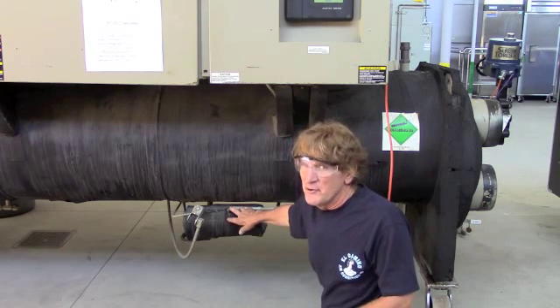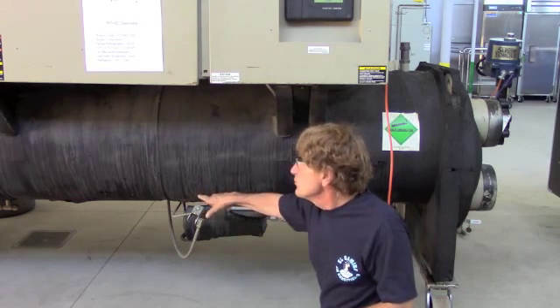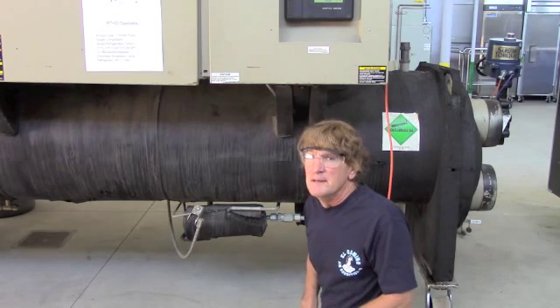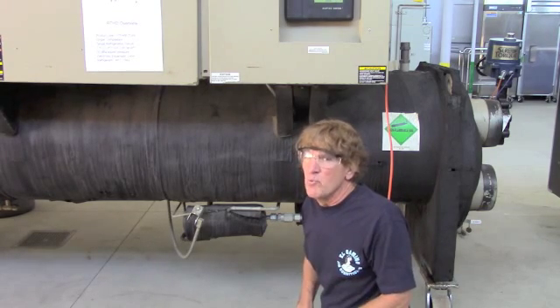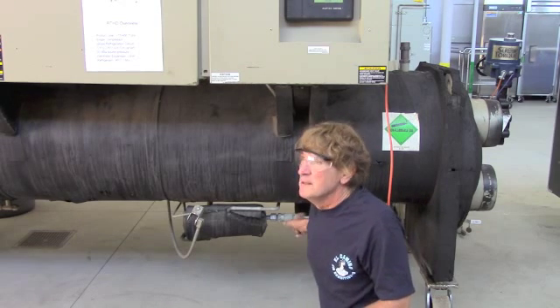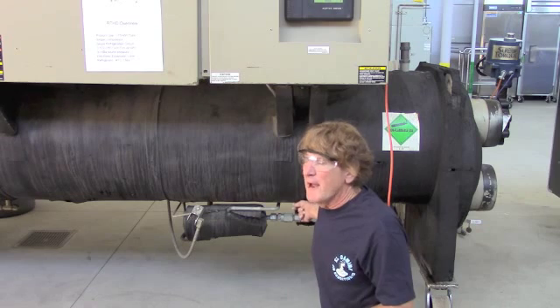Then we will energize another solenoid, and take it straight, which we'll see later, straight up to the compressor again. So we have, basically, two solenoids. One that opens up to the low side, so that we suck in low pressure refrigerant and oil from the evaporator.